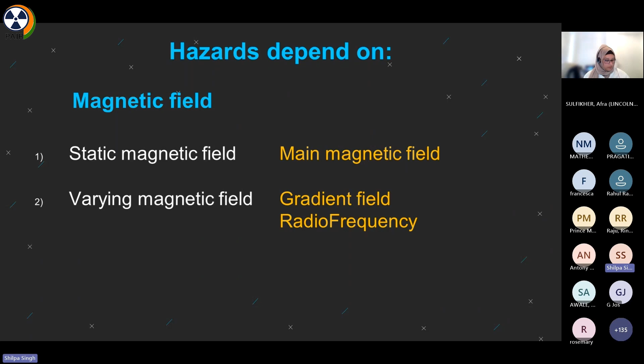Main magnets. Nowadays, we mainly use electromagnets, either superconducting magnets or resistive magnets. They both are essentially electromagnets, a kind of solenoid, which is immersed in cryogens. Cryogens means liquefied helium. Then this liquefied helium is filled in the tank and we use the shim coil either inside, as you see here, or outside the main magnetic field. Why? I'll discuss that later. For now, we will discuss the main magnets.